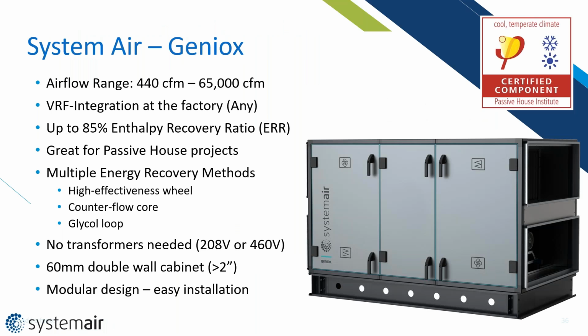This is, like I said, our high effectiveness DOAS option. We have a really big airflow range with this too, from 440 CFM all the way up to 65,000 CFM. And we can do VRF integration at the factory. So this is up to 85% enthalpy recovery ratio, which makes it really good for your passive house projects and otherwise just getting your average up on the enthalpy recovery ratio of the building. So we can do multiple different energy recovery methods with this: high effectiveness wheel, counterflow core, glycol loops. And the cool thing about this too is there's no transformers needed. We can do 208 volt 3-phase, 460 3-phase, no problem, and no electrical issues on site that way.